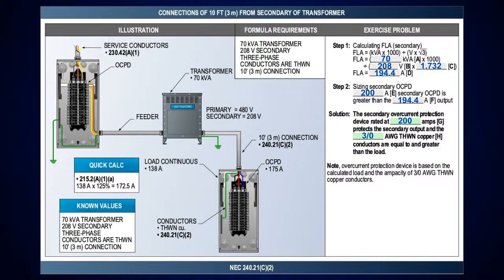Now, this is where we get in. They actually came in, I forget what cycle it was, and a lot of people used to say, oh, just tap the secondary side of that transformer. Well, that didn't make it a tap. Those are actually connections from the secondary of the transformer. So they relayed this article out, specifically 240.21, and that's why we have 240.21(B) and we have (C) now. And this one right here is where we got connections from the secondary of the transformer.